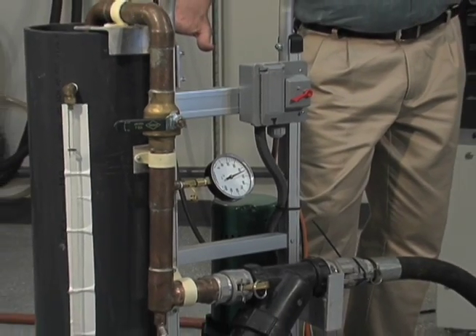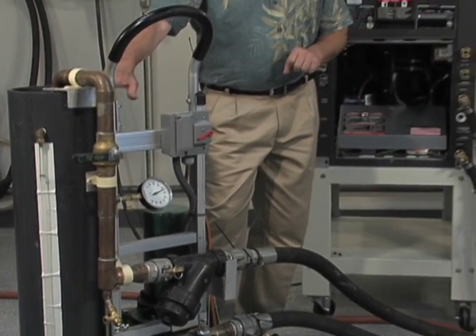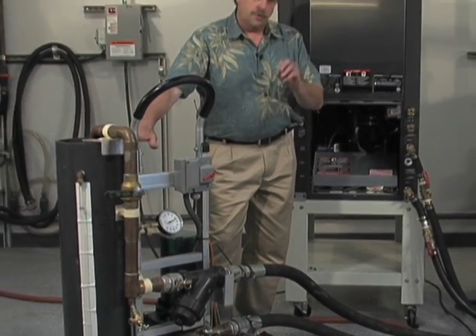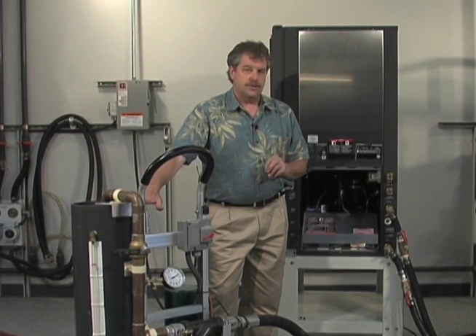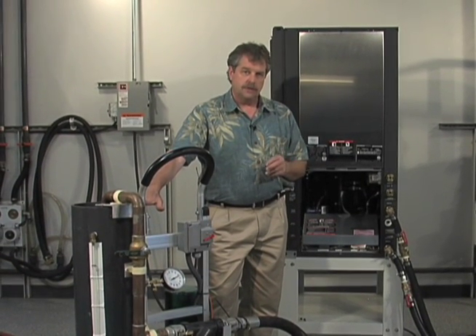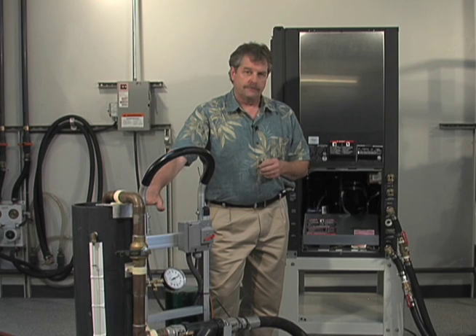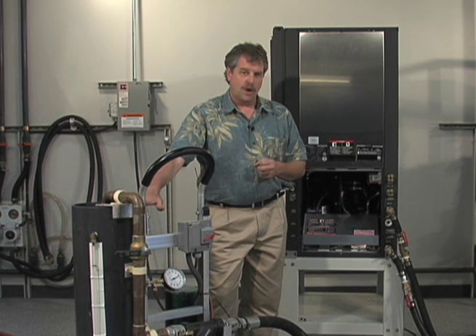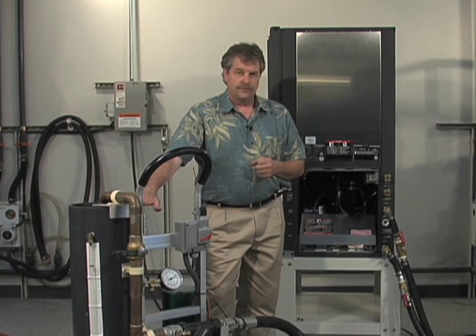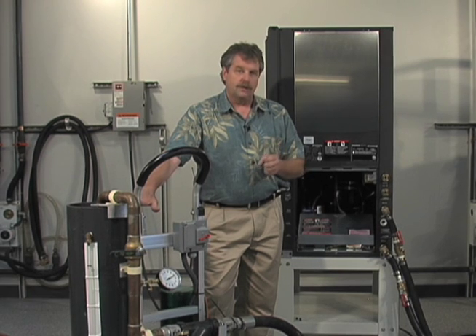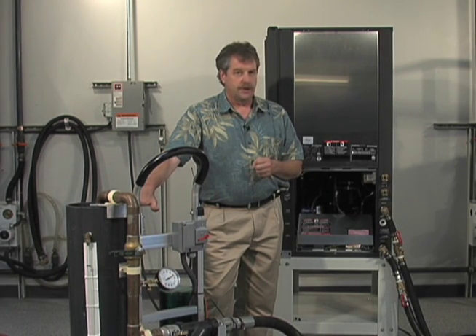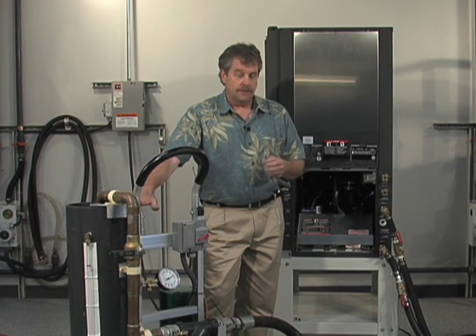And then you're going to want to shut the shutoff valves off over at your flow controller. Again, this component is an integrity test to make sure that we don't have any leaks, and certainly we don't have any air left out there. So leave that gauge in there for a while, probably a good 10 or 15 minutes to see how much tail off you get. We want to see no more than about 3 or 4 psi, has been my experience.